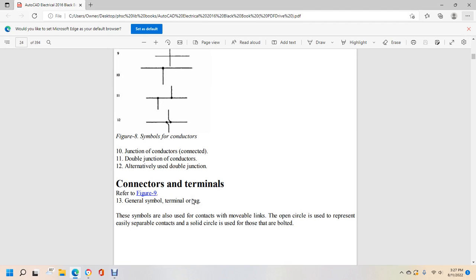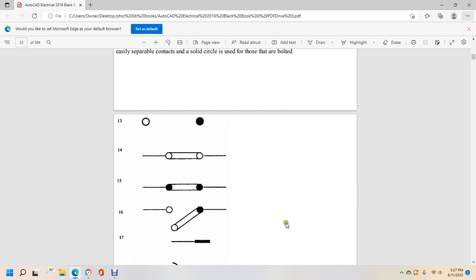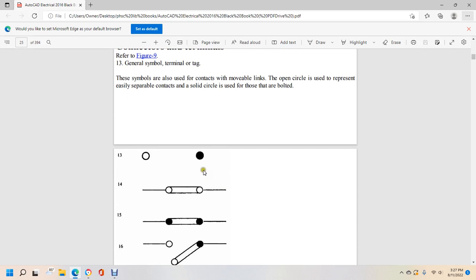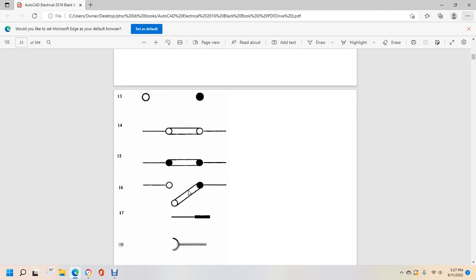Figure 8 shows 10 and 11, which show the junction of the connected conductors, 11 with the double junction of the conductors, and 12, alternate with the double junction. Connectors and terminals. Figure 9 shows the general symbol of the terminal and tag symbol, also with the contact of movable links. An open circle represents an easily separable contact, and a solid circle represents those that are bolted. So a solid circle means that it's fixed, and an open circle represents a contact. It just shows a general connector and terminals.